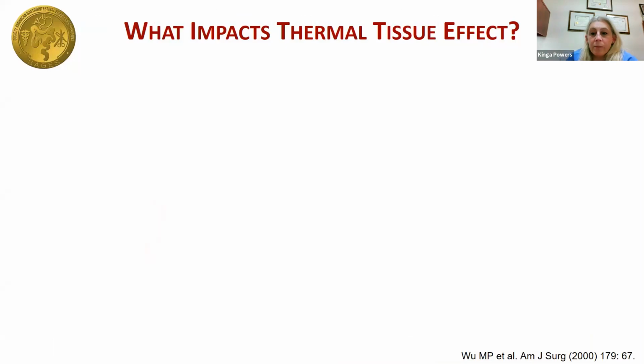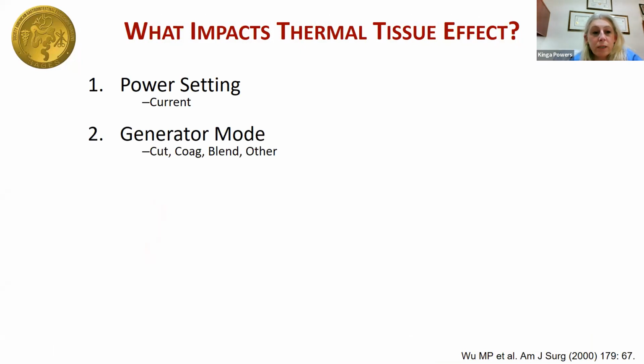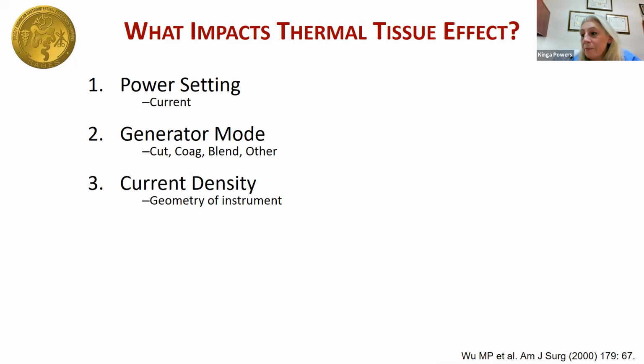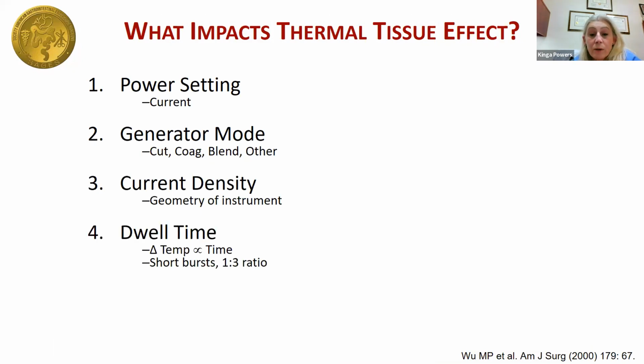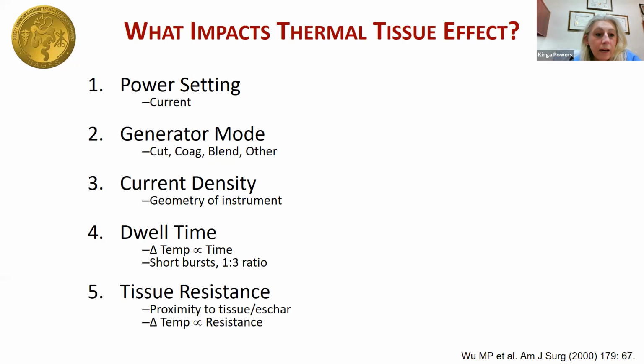To summarize, the things that impact the thermal effect in tissues are: the power setting or watts on your ESU, set on the lowest setting that you can to achieve what you need; the generator mode or duty cycle, such as cut, coag, blend, or other—cut is the low voltage mode; the current density, which is the geometry of your instrument and how you're using it, flat versus a needle point; and the dwell time, how long you hold the button. If you keep the pedal to the metal, you cause a lot more desiccation, wider spread, and more collateral damage. And the tissue resistance, which can be increased by removing things like blood or conductive fluid, and by increasing tissue tension.